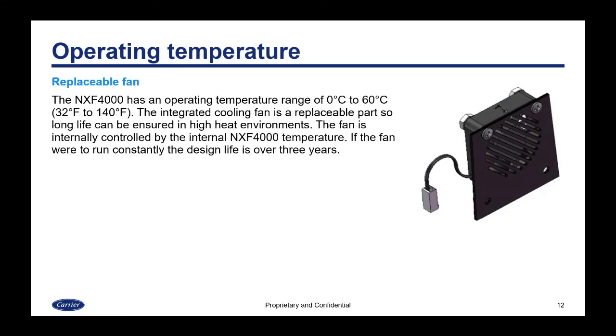The NXF4000 has an operating temperature range of 0 to 60 degrees Celsius or 32 to 140 Fahrenheit. It has an integrated cooling fan that is a replaceable part, so long life can be ensured in high heat environments. The fan is internally controlled by the NXF4000's temperature. If the fan were to run constantly, the design life is over 3 years, but again, it can be replaced, so you don't have to replace the entire control.